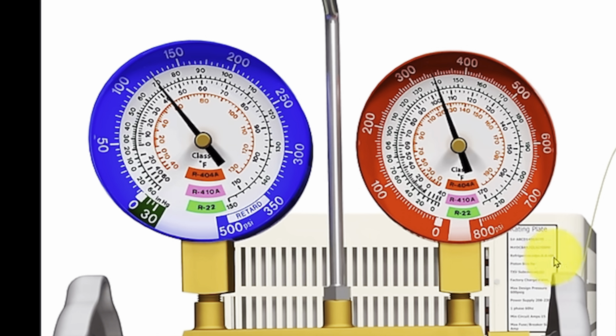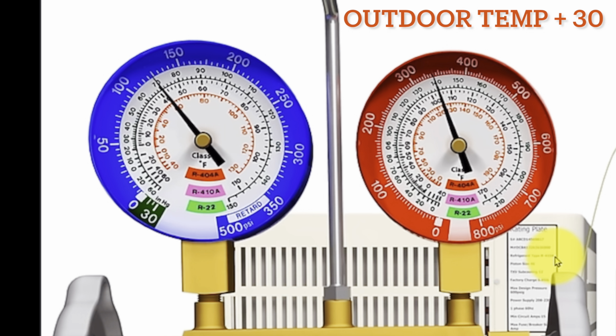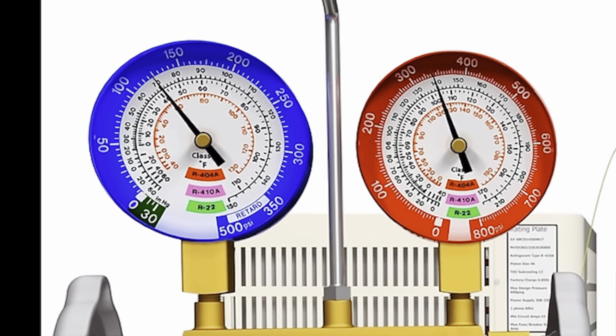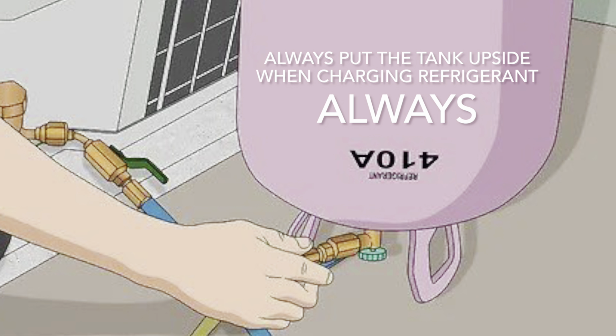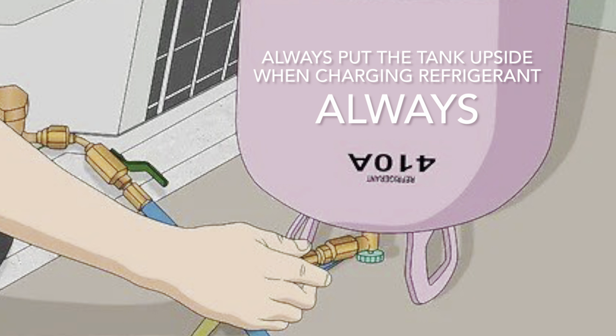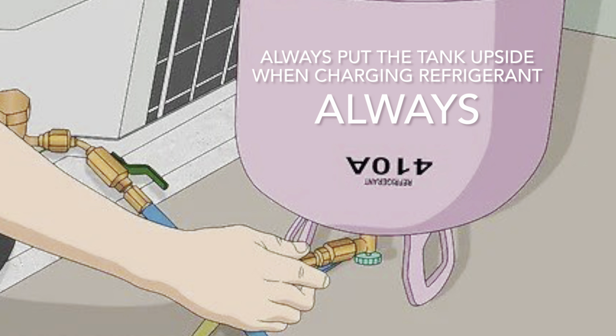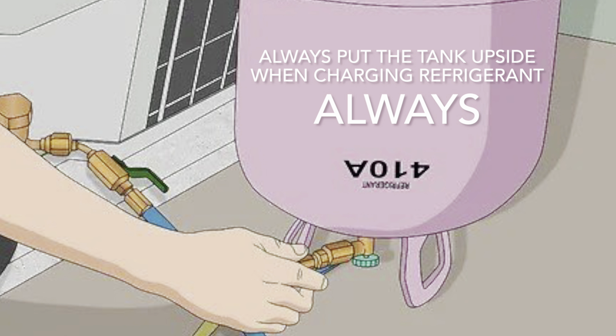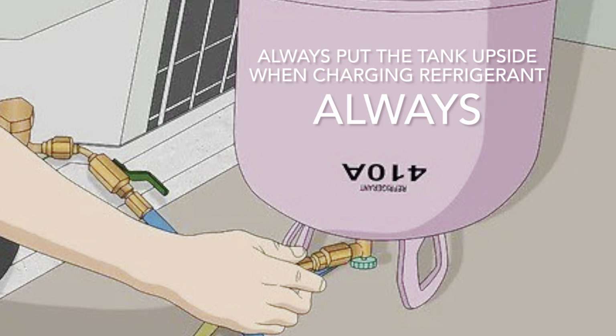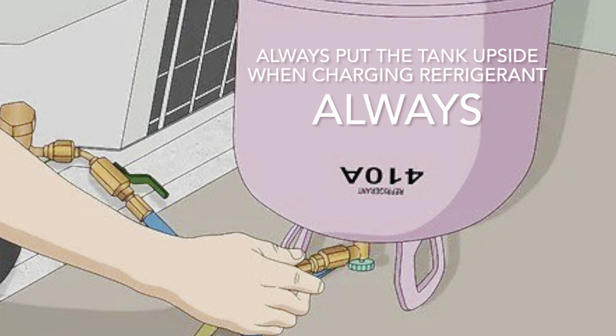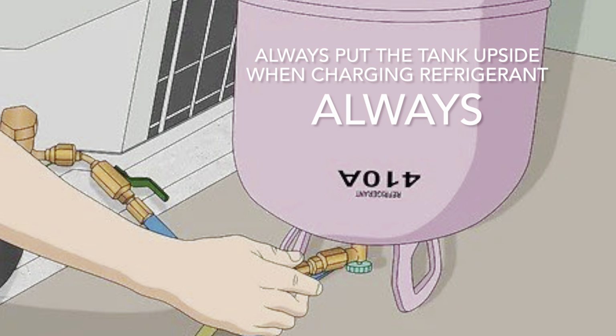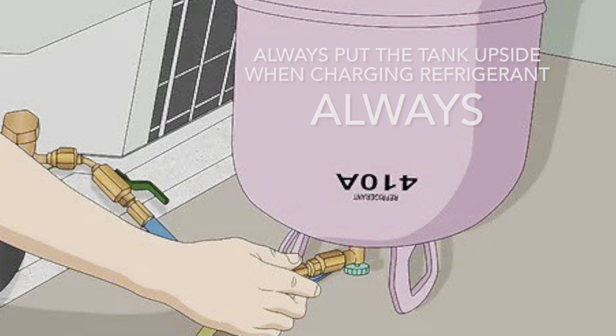If a charge needs to be added, only charge based on the high side. So add 30 degrees to your outdoor temperature, and that'll get you just about where you need to be on the low side. Also, 410A must always be charged with the refrigerant tank upside down, as it is a blend of refrigerants, and as a liquid, it comes out in its purest form of 410A. As a vapor, it does come out with the lightest refrigerant first, so always flip the tank over.